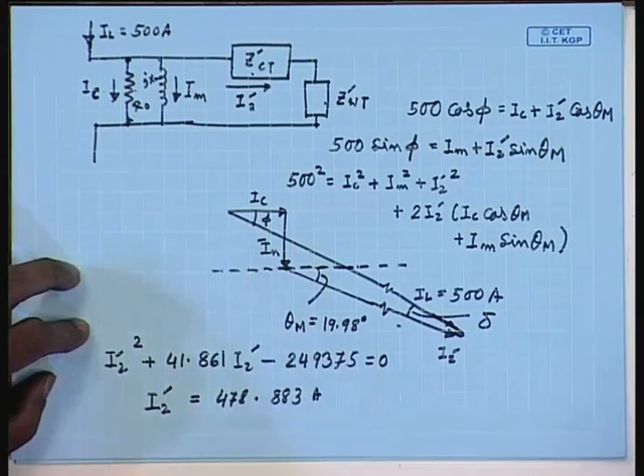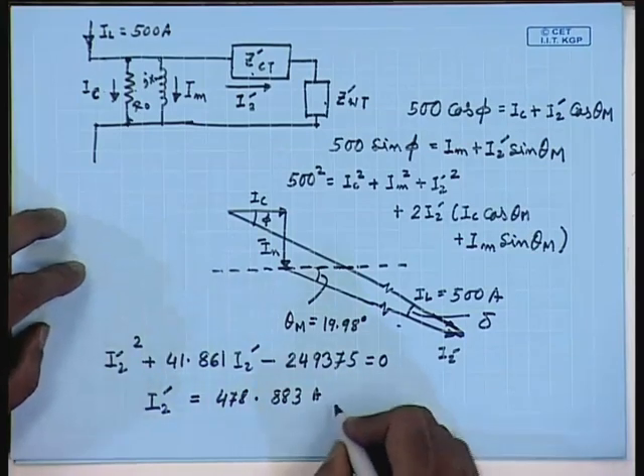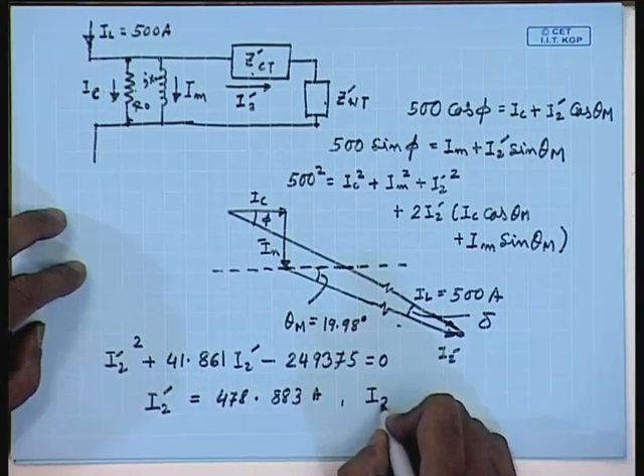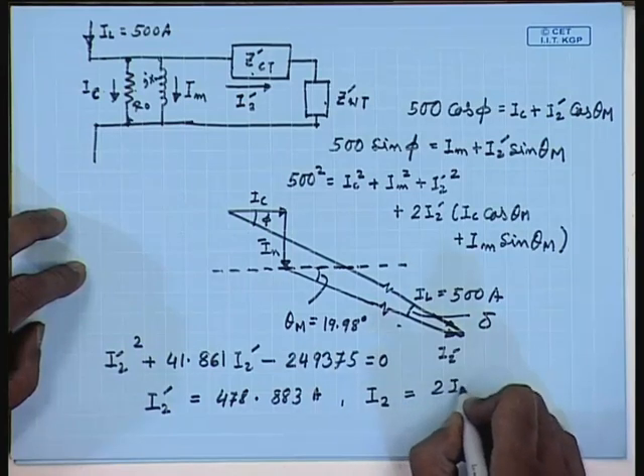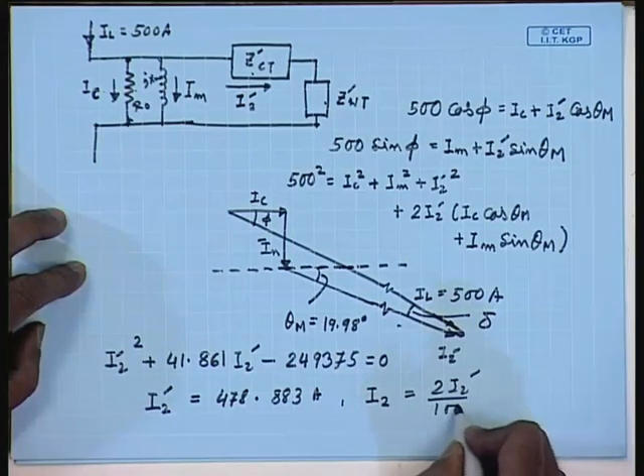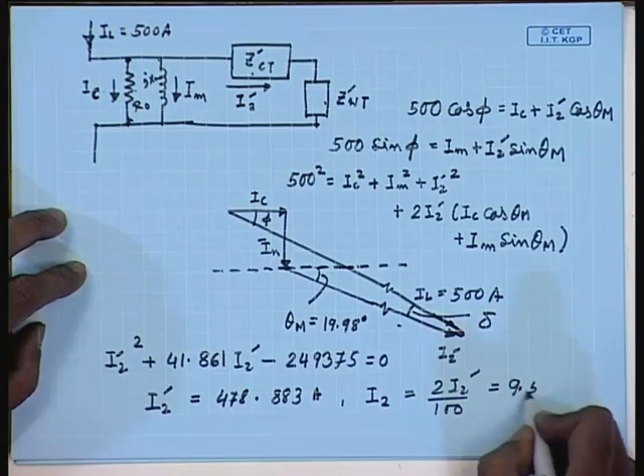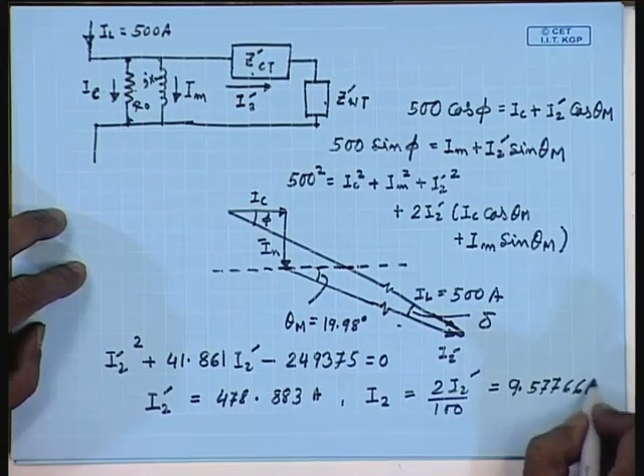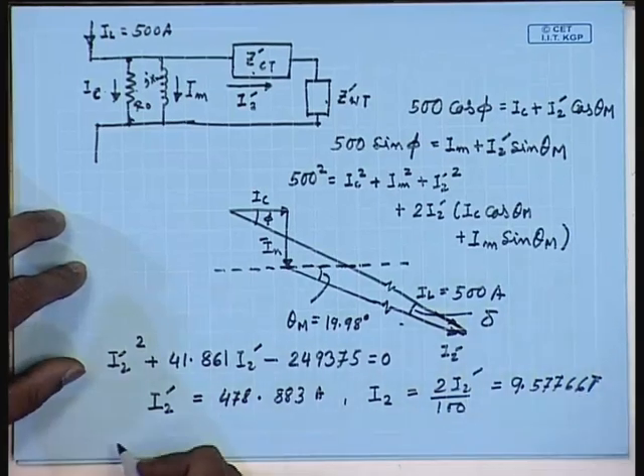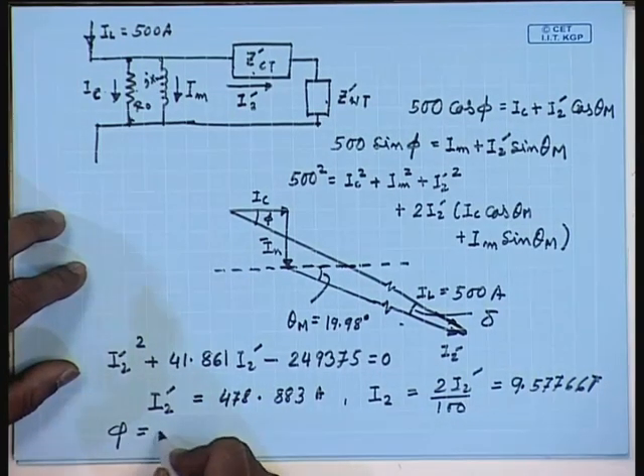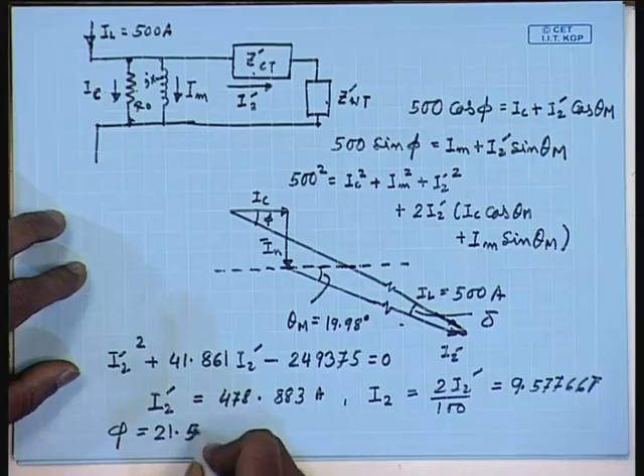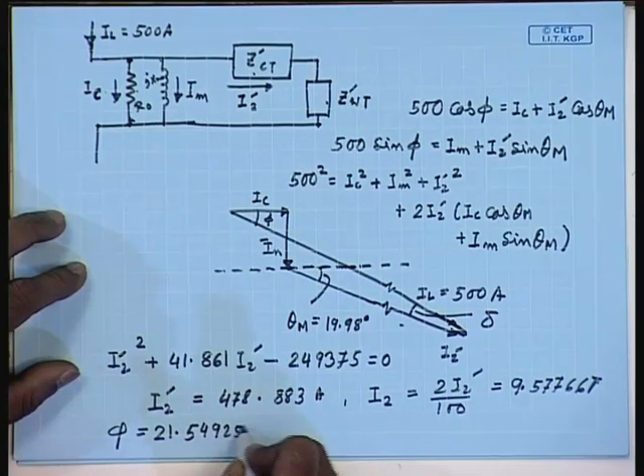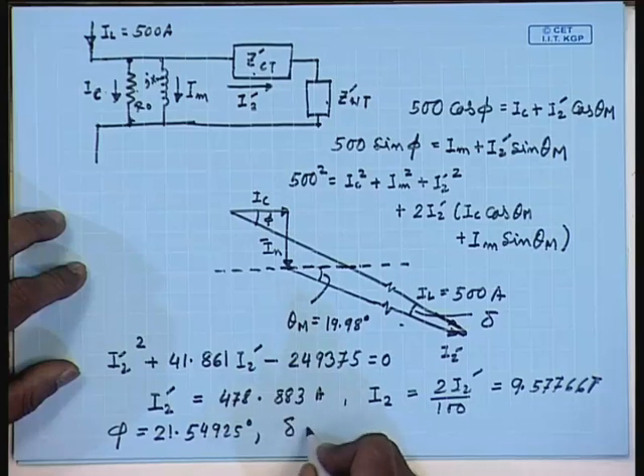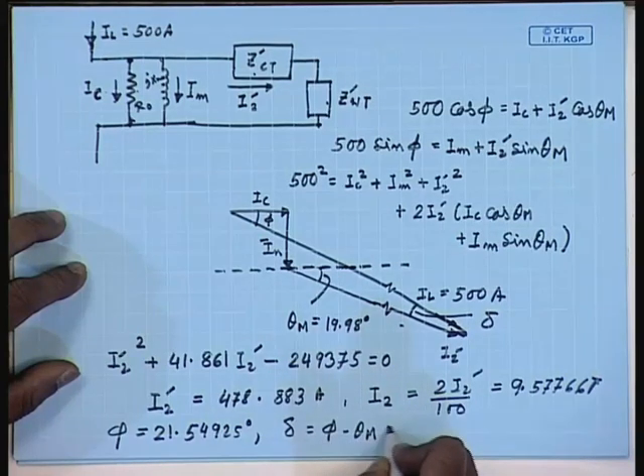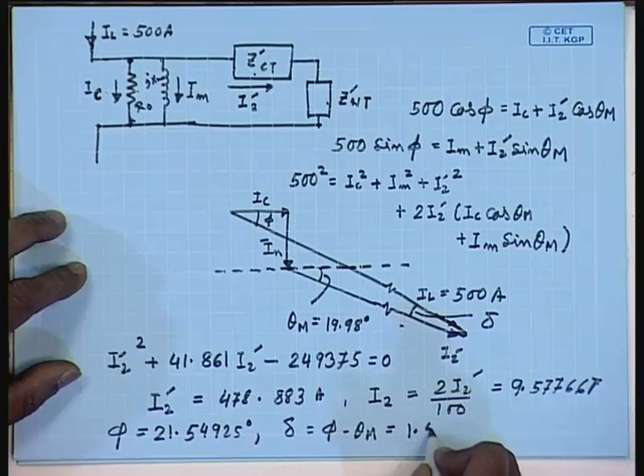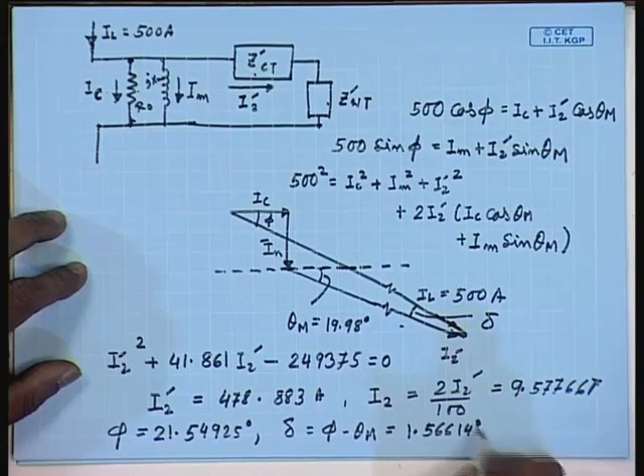478.883 amperes. Hence, the actual current I2 flowing through the meter is 2 I2 dash by 100. That comes to 9.57766 ampere. The angle phi comes to be 21.54925 degrees, and the angle delta, which is phi minus theta m, comes to 1.56614 degrees.